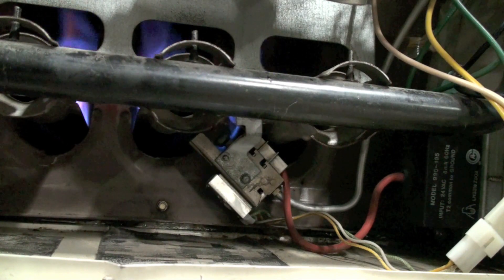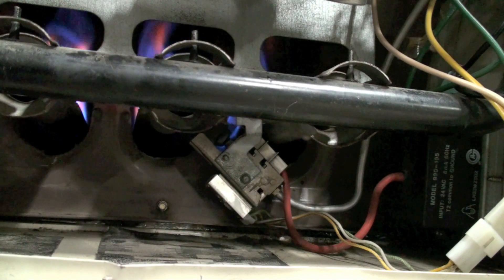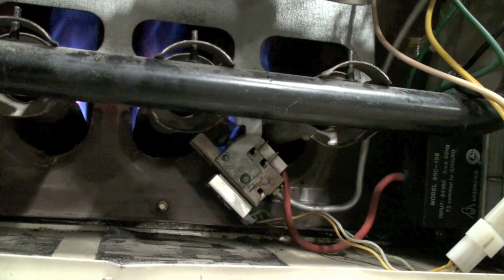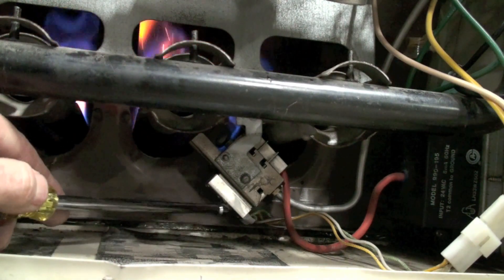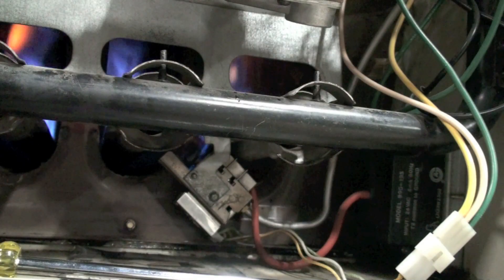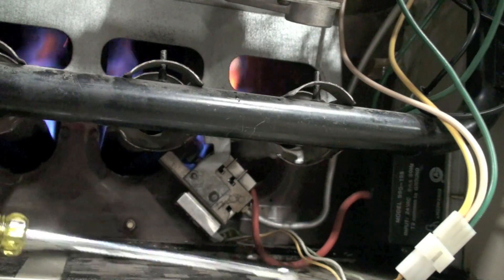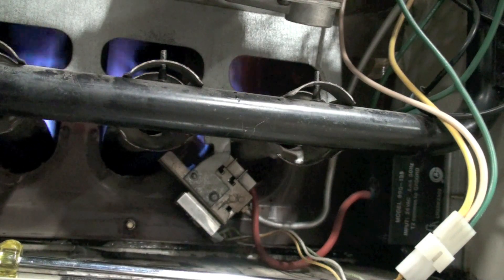If this pilot does not light or the switch here does not work, you have a failure in this pilot assembly and you're going to have to replace that pilot assembly. You can try cleaning it if the pilot light is yellow and lazy.